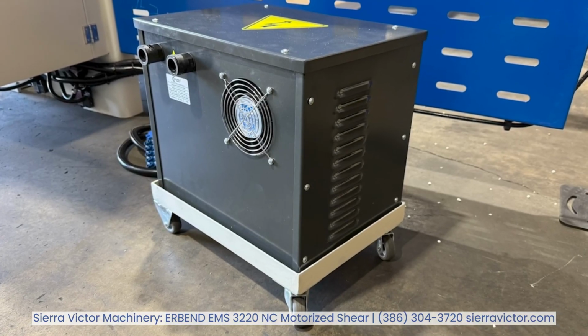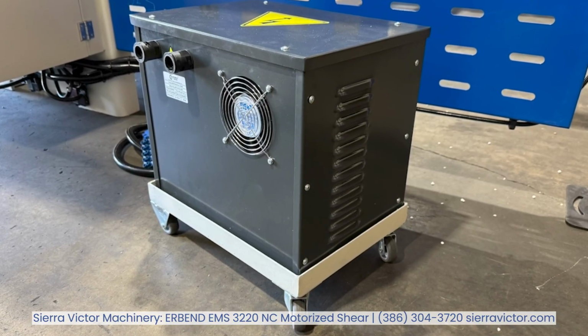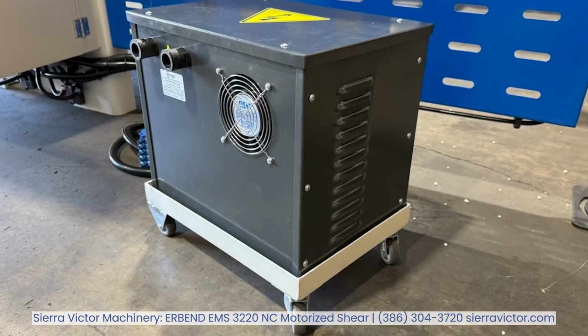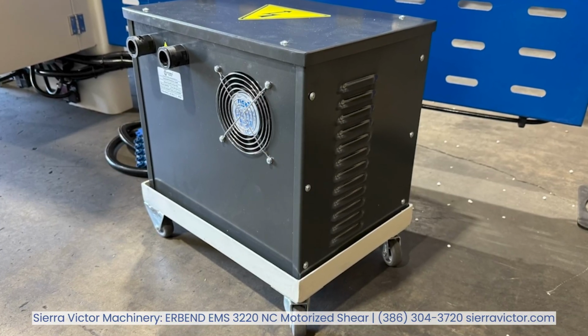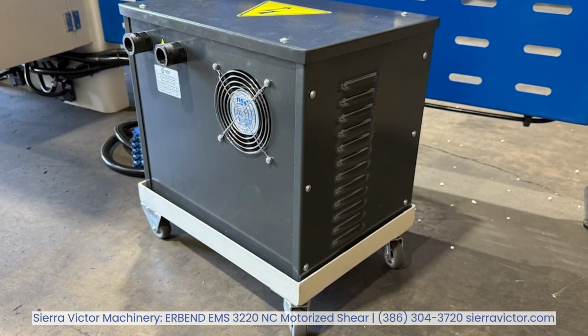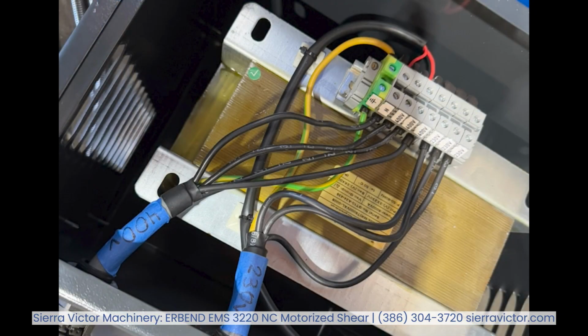The machine requires the use of an included transformer mounted on a rolling shelf to operate at 230 volts and 3-phase. The licensed electrician must ensure that the correct 3-phase power is being supplied to the machine, then use a properly sized power cord to wire into the machine. Note the location of the 400 volt versus 230 volt pigtails inside the transformer during install as pictured.